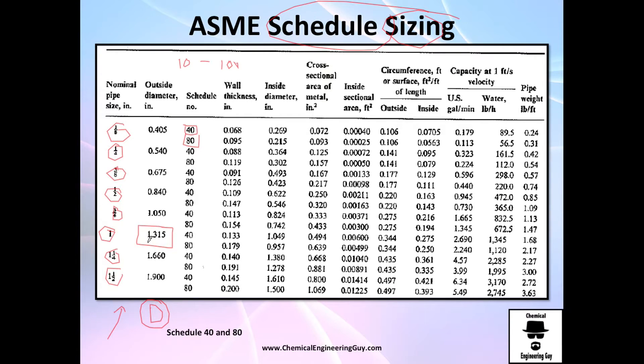This cover is 1.315 inches in outside diameter. Depending on whether you choose schedule 40 or schedule 80 — if you choose schedule 40, you get a little less thickness; if you choose schedule 80, you get a thicker material. You want thicker material for applications with heat exchange or high pressures. The inside diameter also has nothing to do with the nominal one-inch — for schedule 80, it's almost less than one inch.